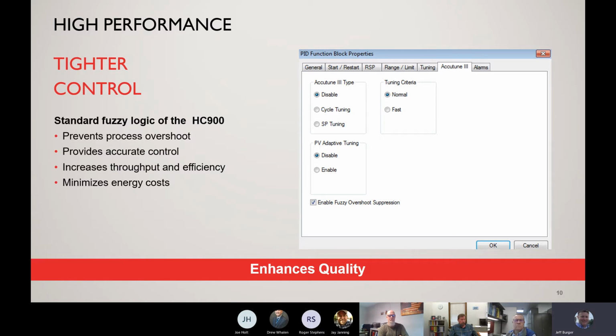A couple of the other features of the software that's very important, especially in process control. The process control loop will allow you to do auto tune. It'll also have the standard fuzzy logic, and the fuzzy logic prevents the overshoot of process. This actually operates separate from your tuning, and it gives you a little bit more of an advanced type of online tuning, which allows for very quick control that allows you to come back to set point, and it minimizes any overshoot or undershoot of that process variable, so that it keeps real good quality control of the process.